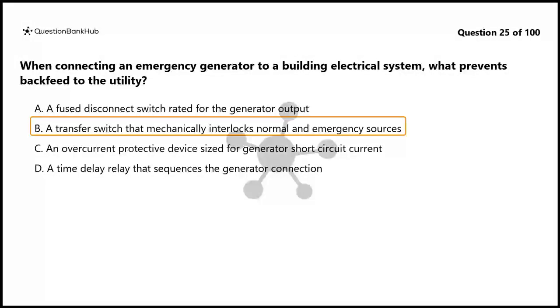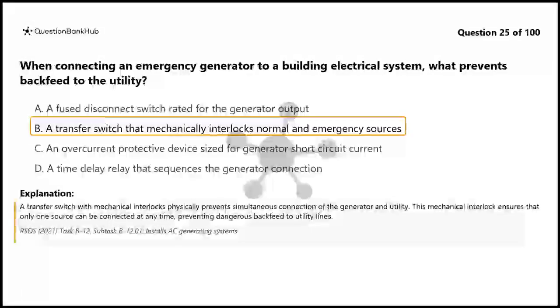The correct answer is B. A transfer switch that mechanically interlocks normal and emergency sources. A transfer switch with mechanical interlocks physically prevents simultaneous connection of the generator and utility. This mechanical interlock ensures that only one source can be connected at any time, preventing dangerous backfeed to utility lines.